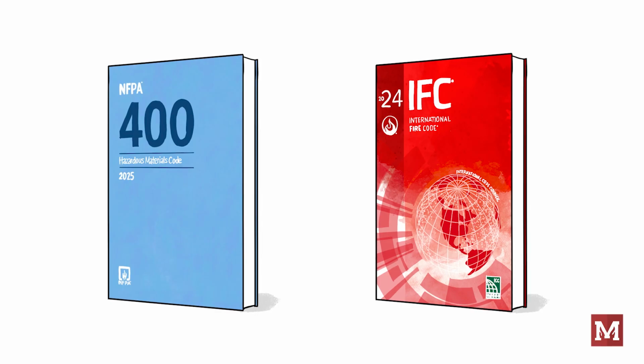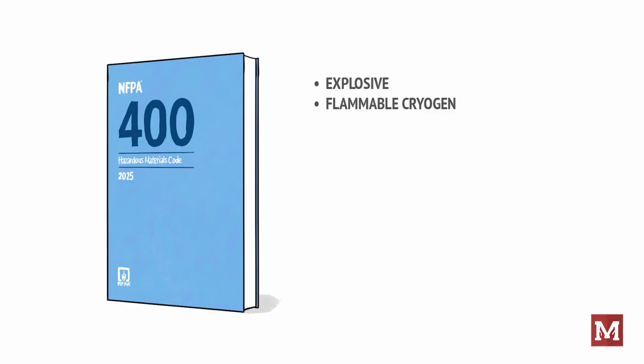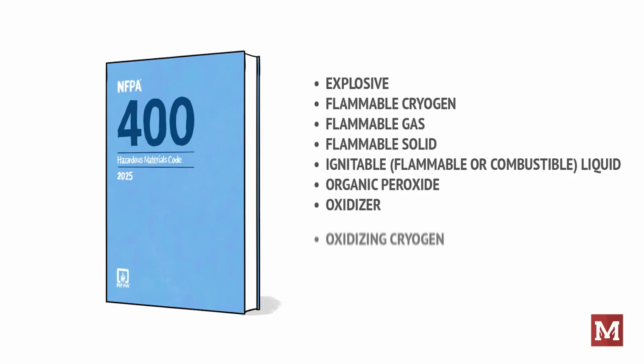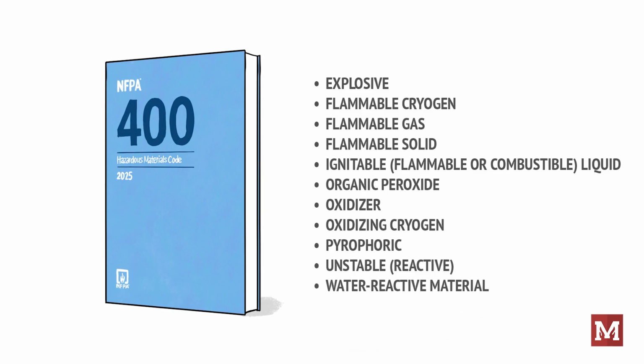Physical hazards, as defined by NFPA 400, are a chemical substance classified as an explosive, flammable cryogen, flammable gas, flammable solid, ignitable liquid, which is a flammable or combustible liquid, organic peroxide, oxidizer, oxidizing cryogen, pyrophoric, unstable reactive, or water reactive material.